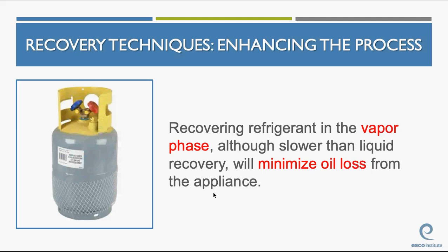Recovering refrigerant in the vapor phase, although slower than the liquid phase, will minimize oil loss. So if you're worried about losing oil out of a system, and you know these systems when you're in the field, then you recover in the vapor phase. It's a much slower process, but it pulls less oil out of the system. Okay? And again, gravity comes into play here. Oil will follow gravity.